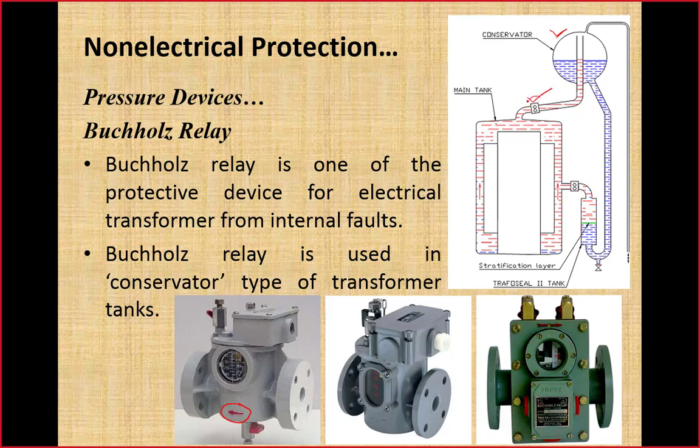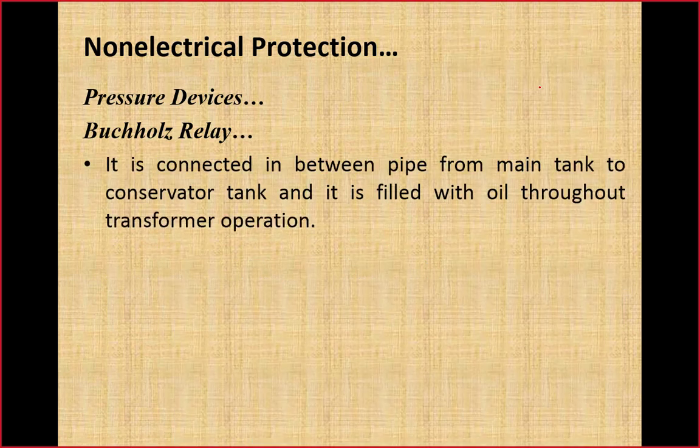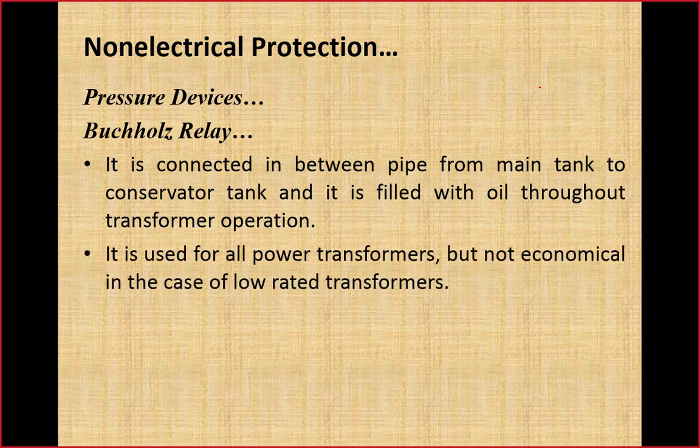So on this path we have installed the Buchholz relay. This is the Buchholz relay, and this Buchholz relay is installed at an angle with respect to the horizontal axis like this, and normally this angle will be around 15 degrees. It is connected in the pipe between the main tank and the conservator tank, and it is filled with oil throughout transformer operation. So it is used for all power transformers but is not economical in the case of low rating power transformers.